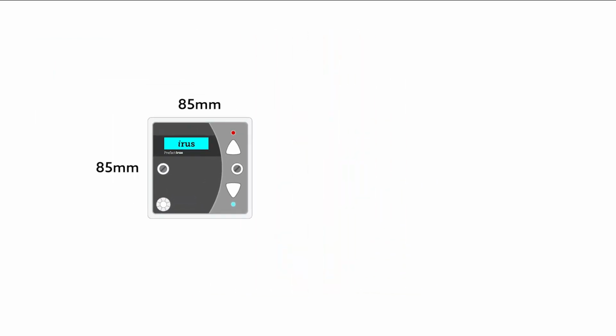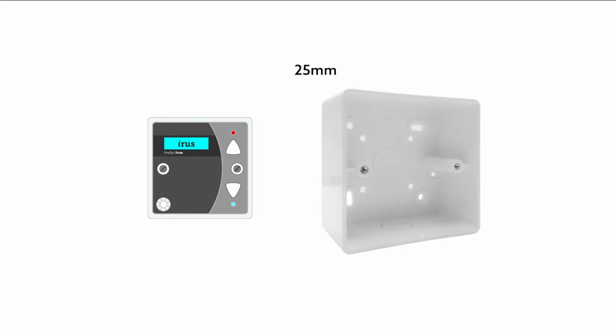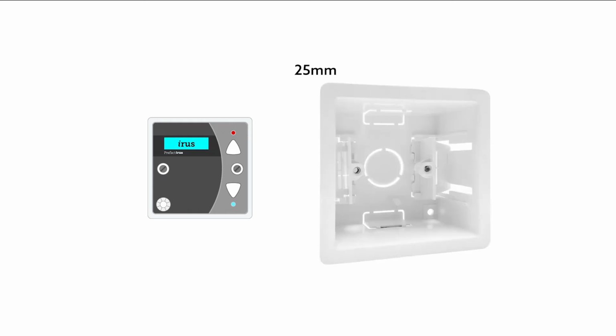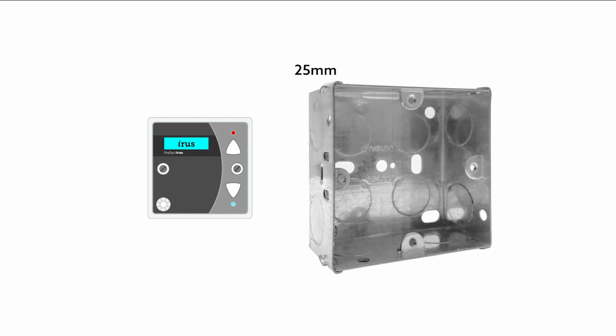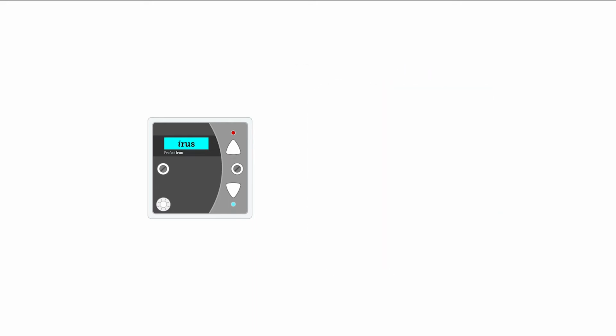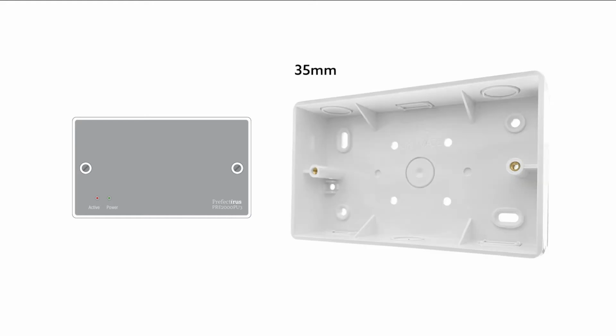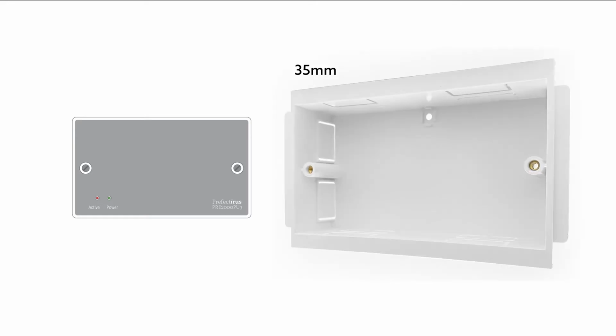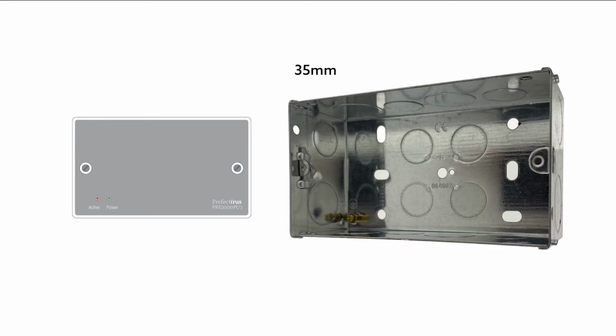The control unit is 85mm square. It is a standard single gangplate size and requires a 25mm deep surface pattress, dry lining plastic box, or metal sunken box with 2 mounting points. If they have 4 lugs, remove the top and bottom ones. The power unit, slave relay, and probe interface unit dimensions are 146mm by 85mm, and they are a standard double gangplate size. They require a 35mm deep surface pattress, dry lining plastic box, or metal sunken box with 2 mounting points.